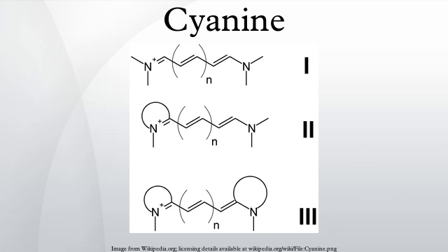Cy5 became very popular to replace far-red fluorescent dyes, because of its high extinction coefficient and because its fluorophore emission maximum is in the red region, where many CCD detectors have maximum sensitivity, and biological objects have low background. The scanners actually use different laser emission wavelengths and filter wavelengths to avoid background contamination. They are thus able to easily distinguish colors from Cy3 and from Cy5, and also able to quantify the amount of Cy3 and Cy5 labeling in one sample.